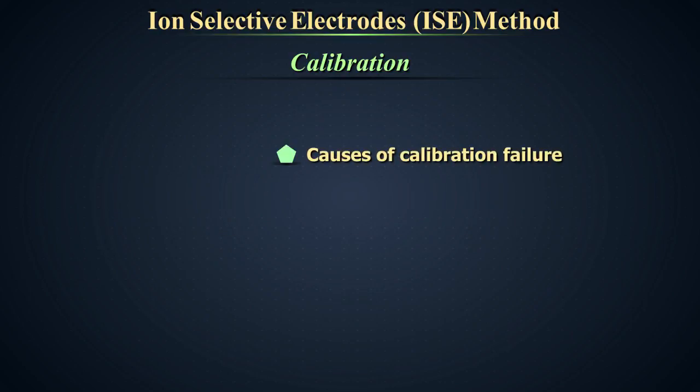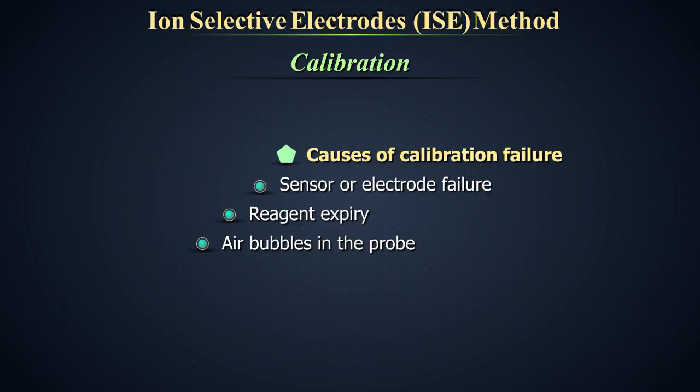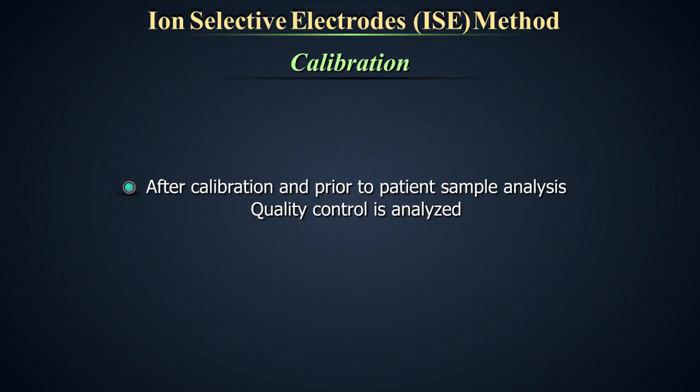Few causes of calibration failure are sensor or electrode failure, reagent expiry, air bubbles in the probe. After calibration and prior to patient sample analysis, quality control must be analyzed to establish the equipment's performance.